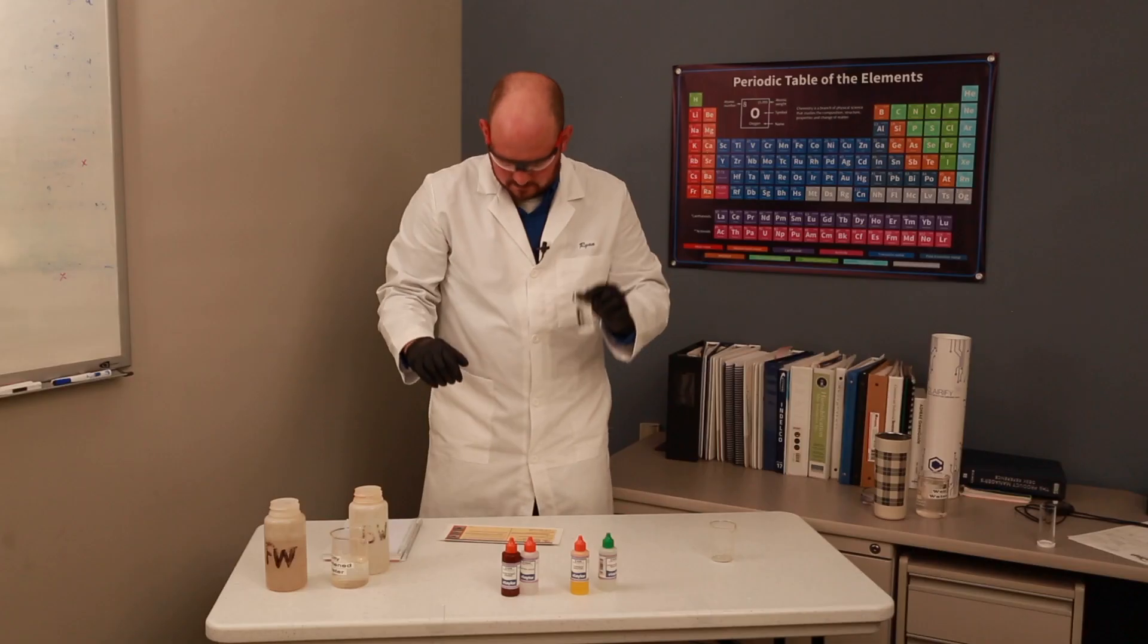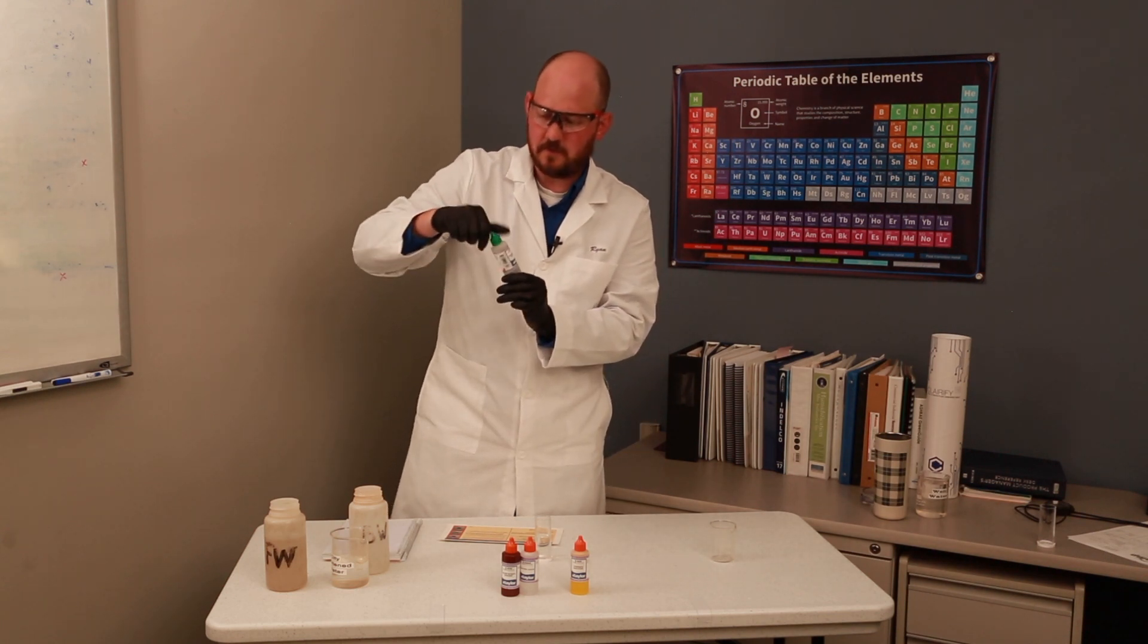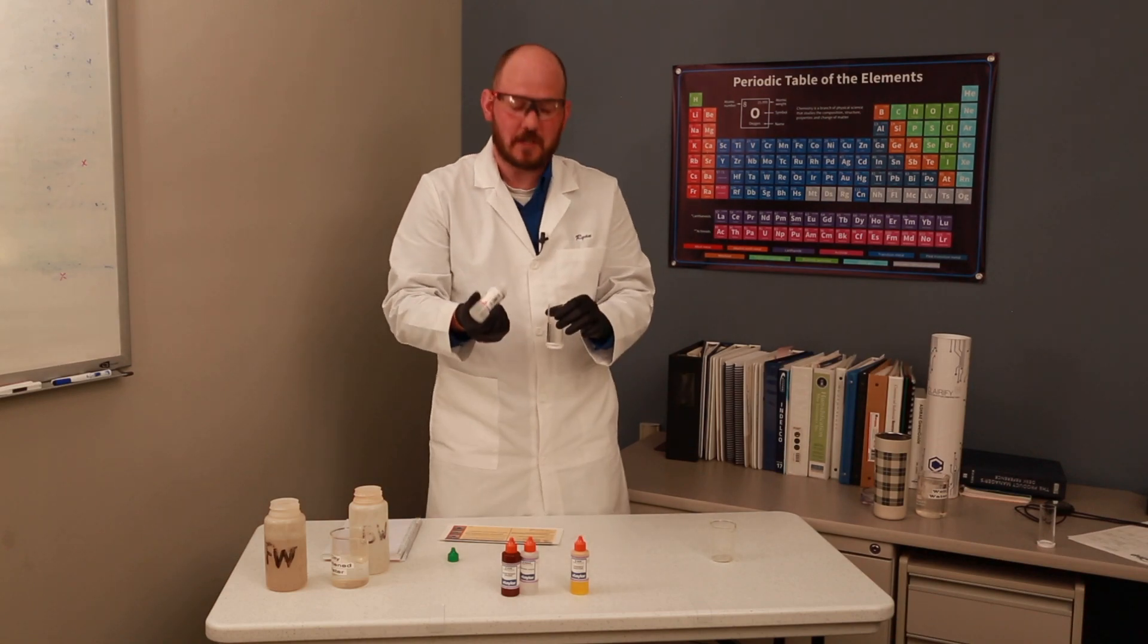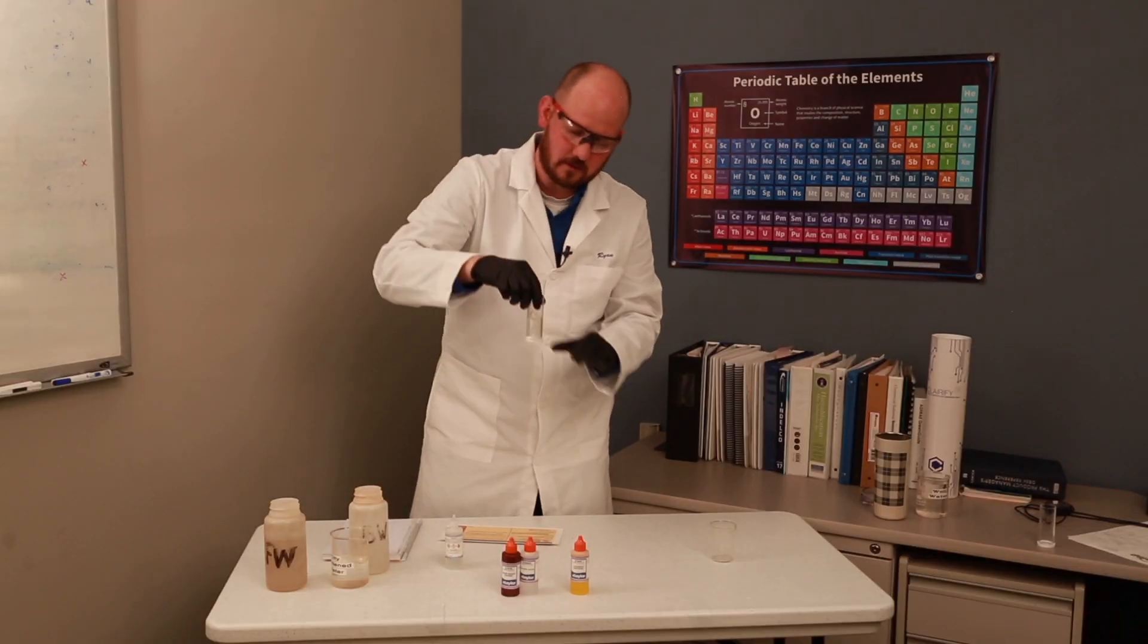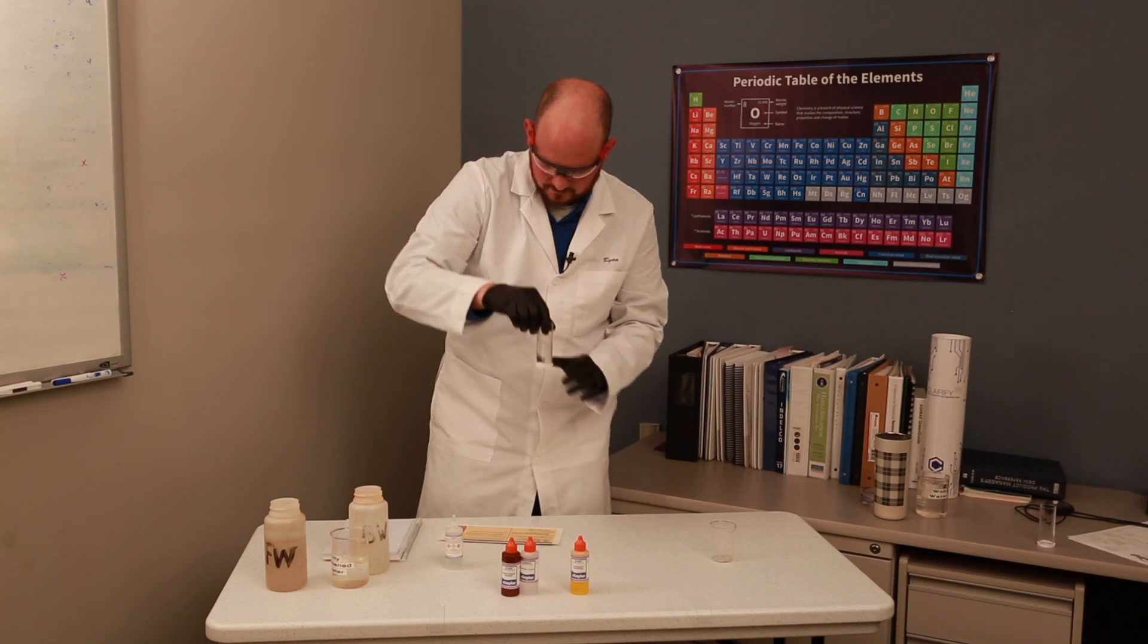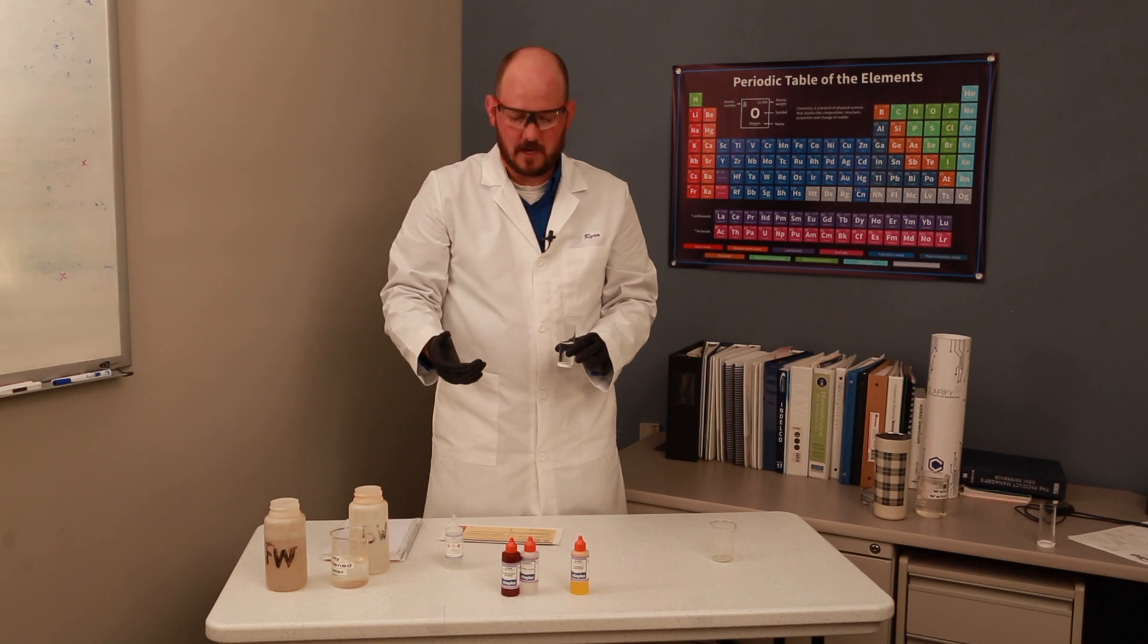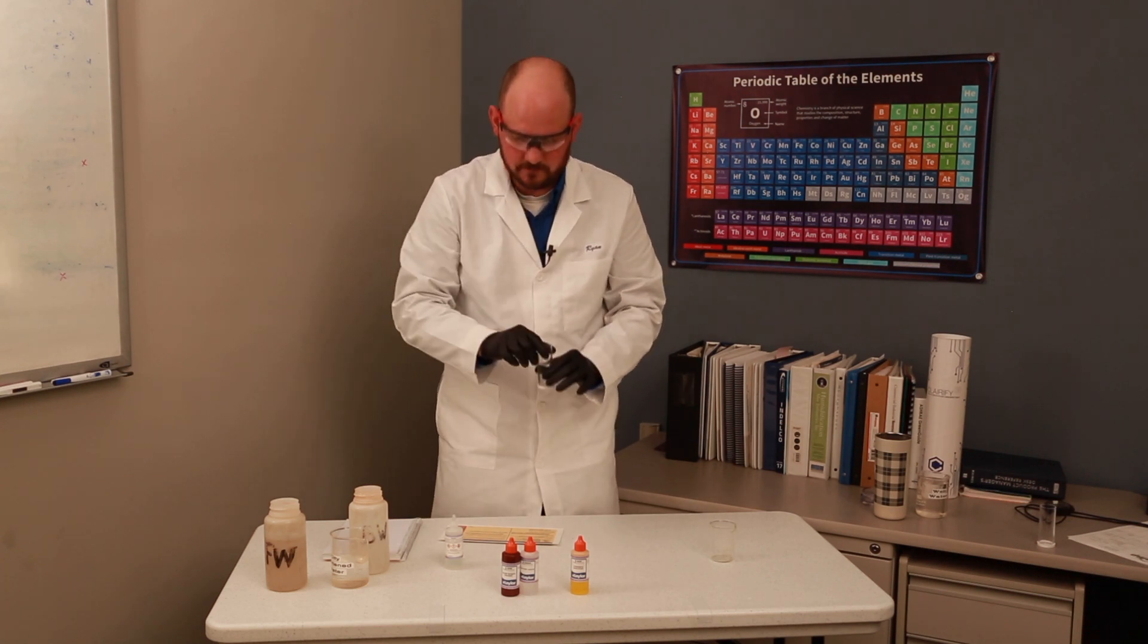The first step is to add phenolphthalein, which is this green-capped one in this case. If you bought just the chloride test kit, it would come with an orange cap. Adding two drops - if it turns colorless, we are good and can skip the next step. If this was to be pink, then we would add sulfuric acid, which I will show subsequently.